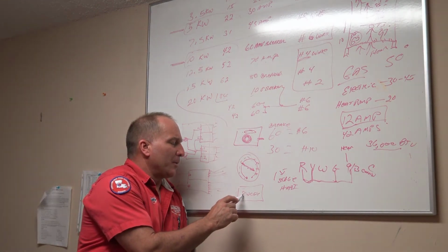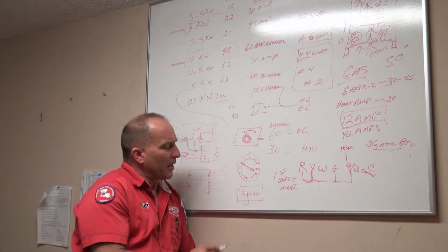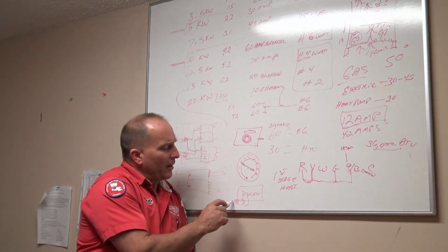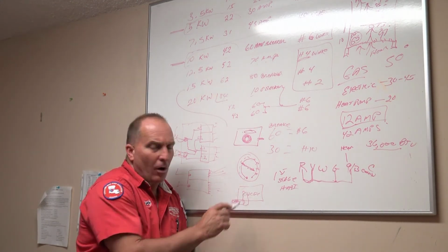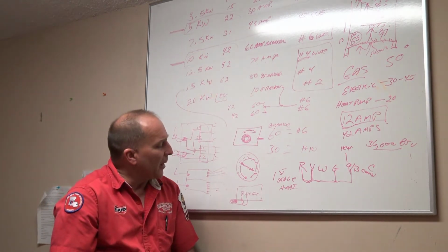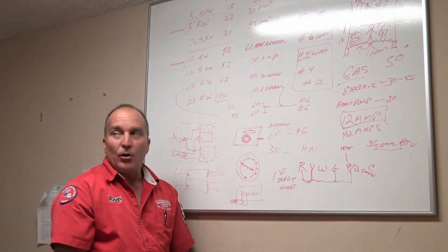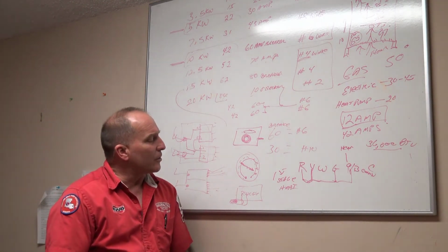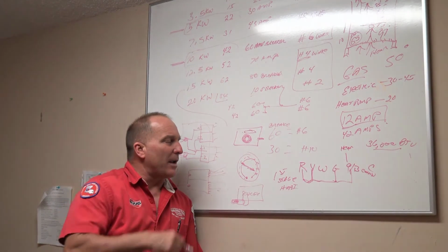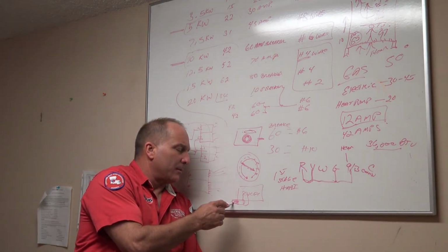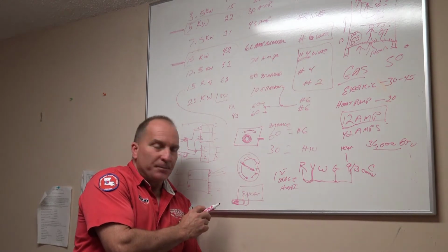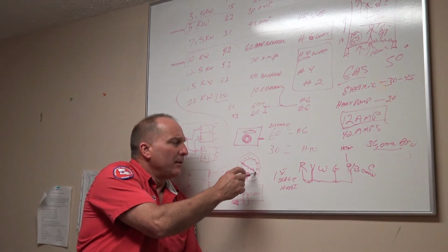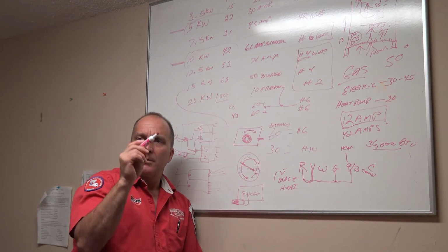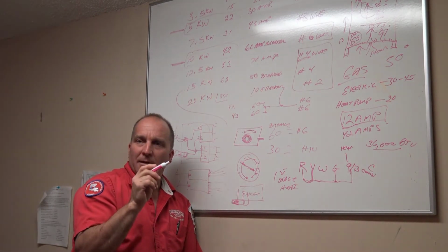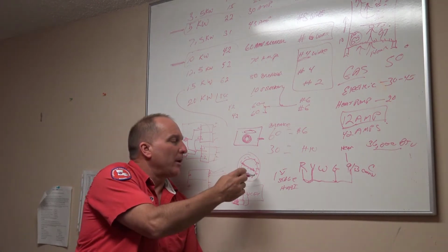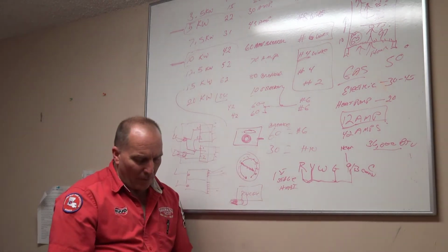Then you take your amp probe and a low voltage wire and you go from R to W and put your amp probe on there, and you are going to read the amperage draw between R and W. When you read the amperage draw between R and W, you have to wait till all heat sequencers are energized, and then whatever amperage comes up on your amp probe meter is what you point this to. So if it says 0.09 and then 8 and then 7 and then at the end of it it's 0.04, you point it to 0.04.